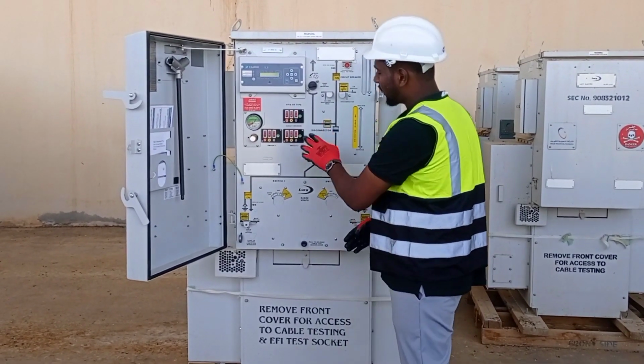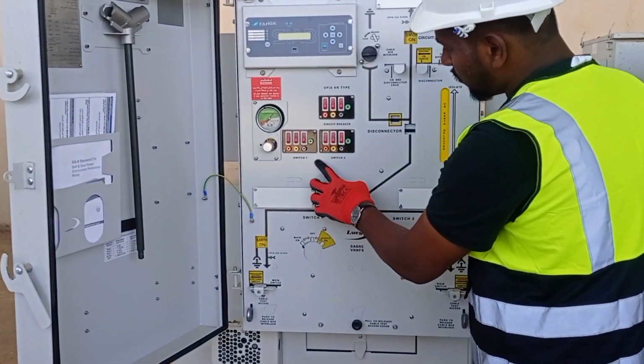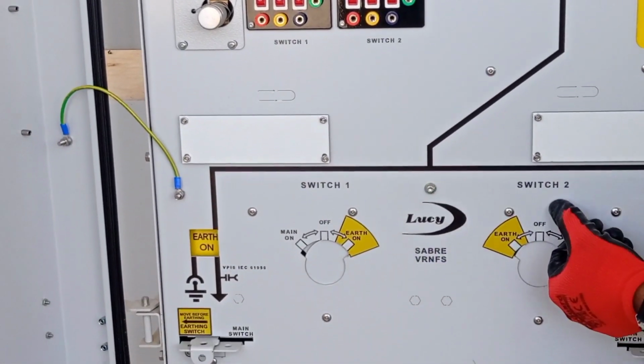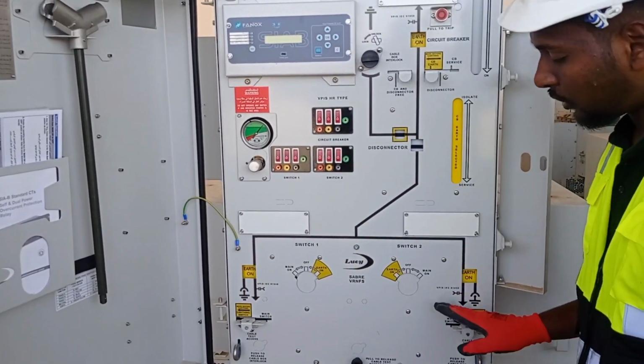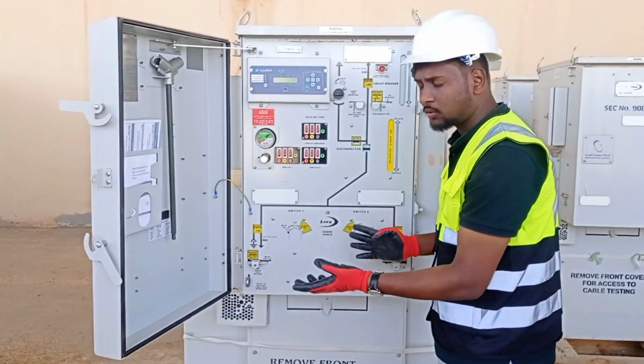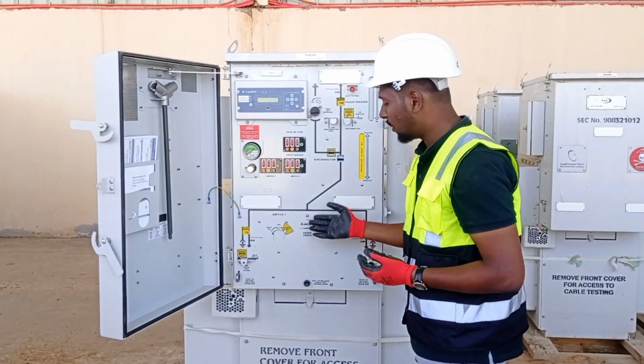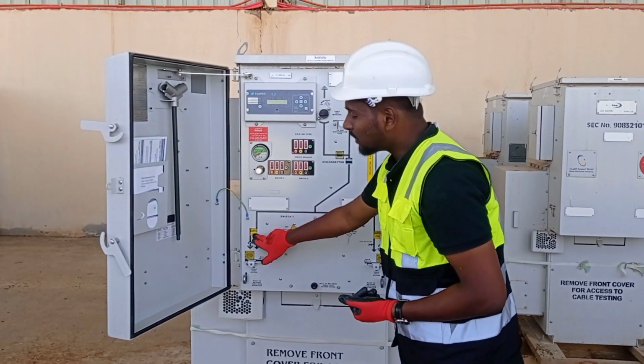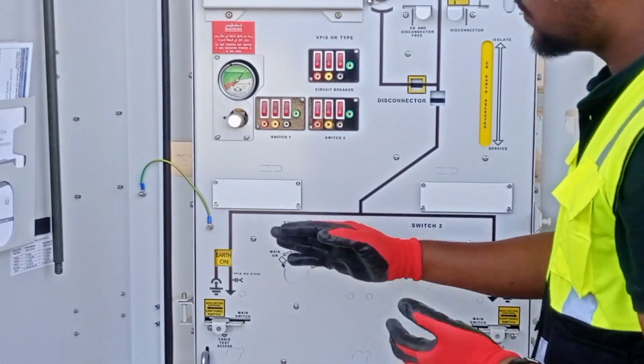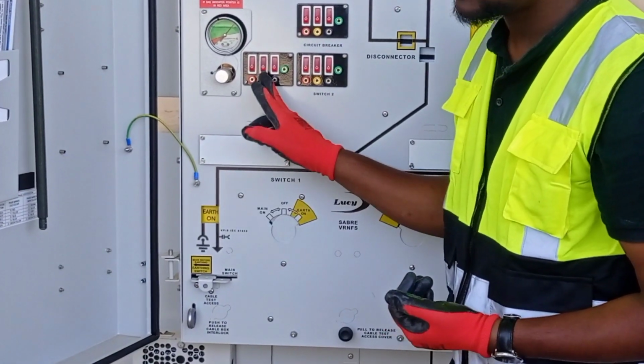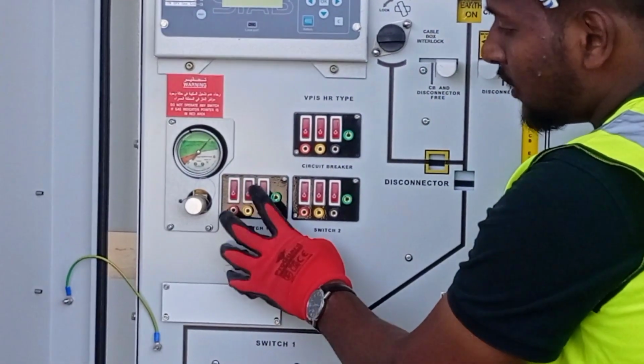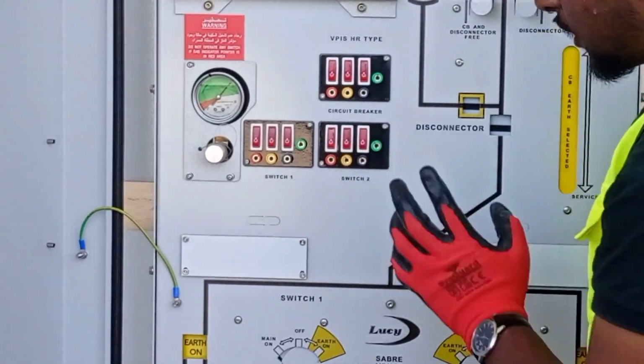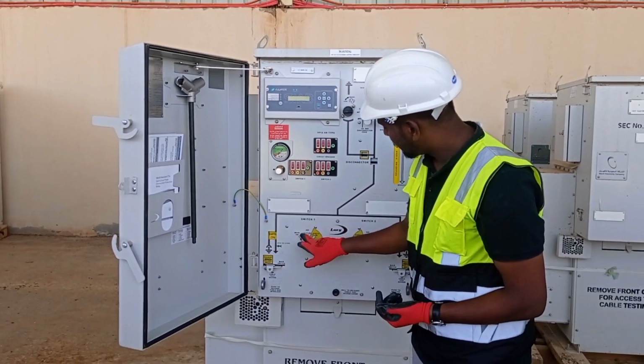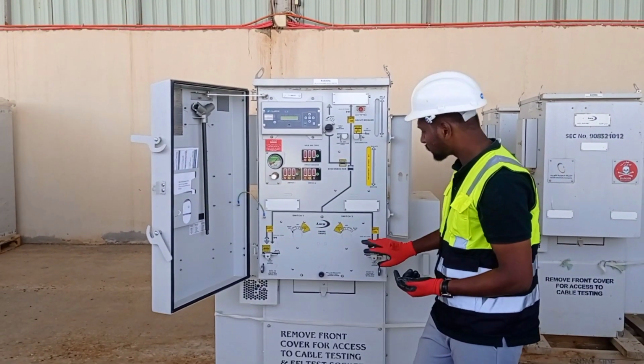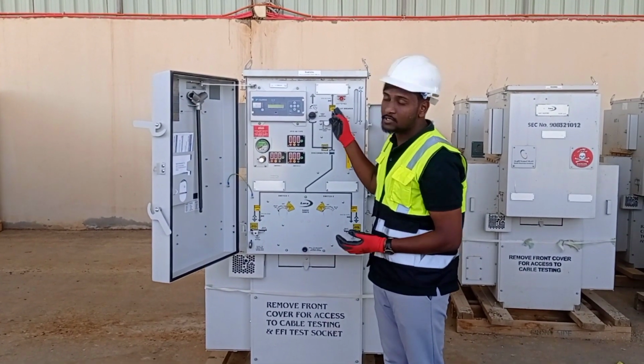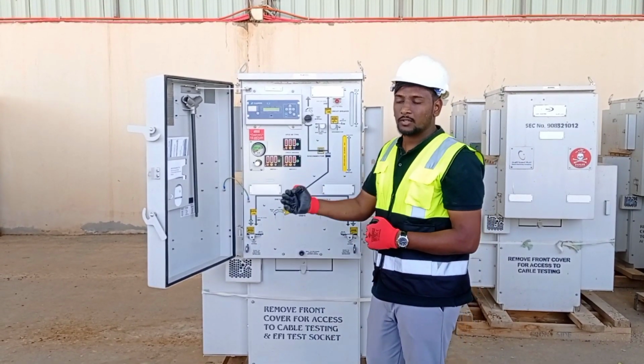There are many indications here also. We can see circuit breaker, switch one, switch two. Switch 1 and switch 2 are also mentioned here. As I told you before, we use these as incoming and outgoing. No problem, we can shuffle them. We can use this as incoming and this as outgoing, whatever we need. Once we make the termination and it is finished, once we energize this, we can check the supply by switching here. This indicates the three phases R, Y, B, and this indicates the other phases. This one represents switch 1 and this one represents switch 2. Then, as I told you before, this is always used to connect with the transformer side.